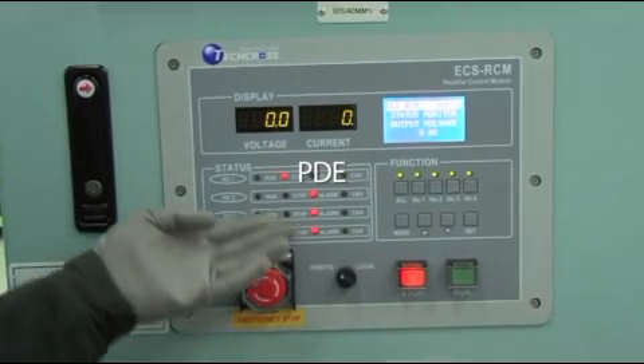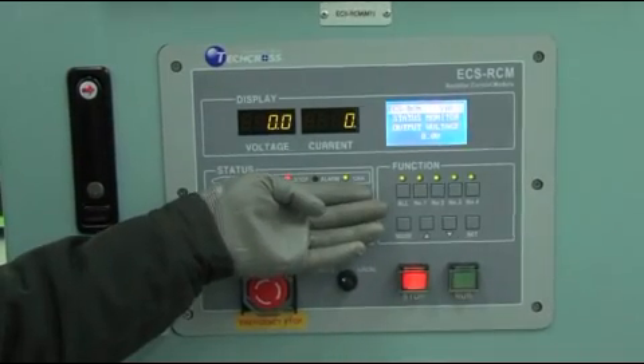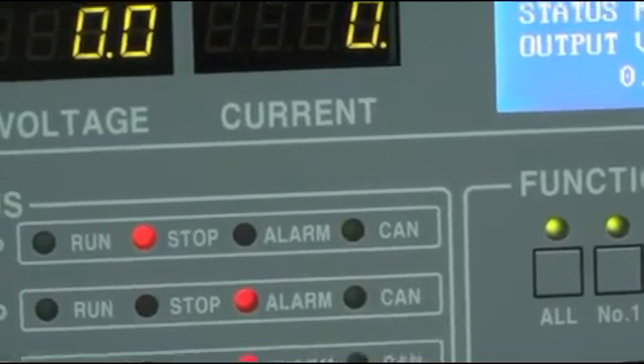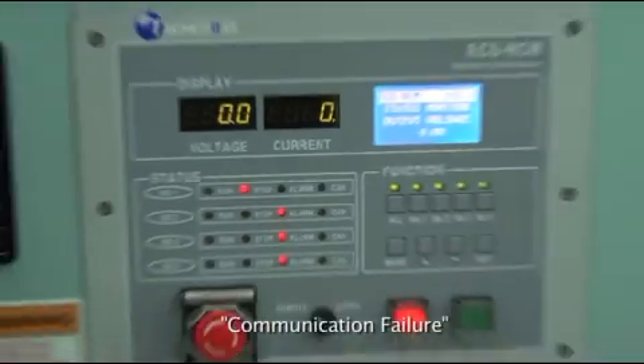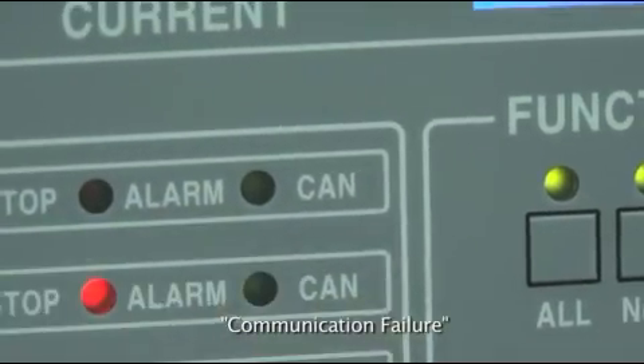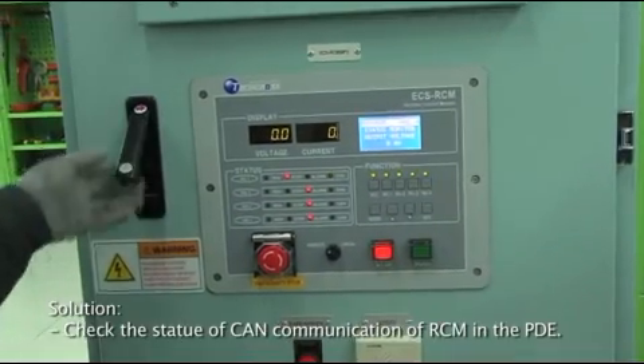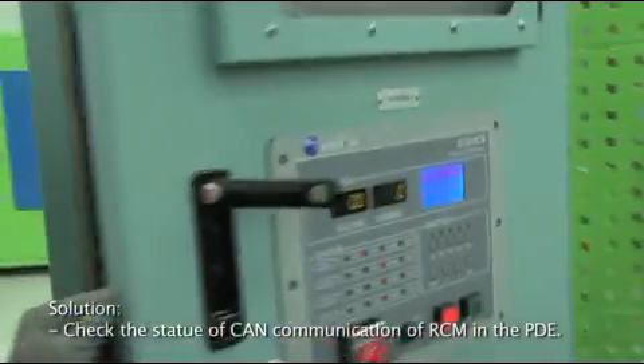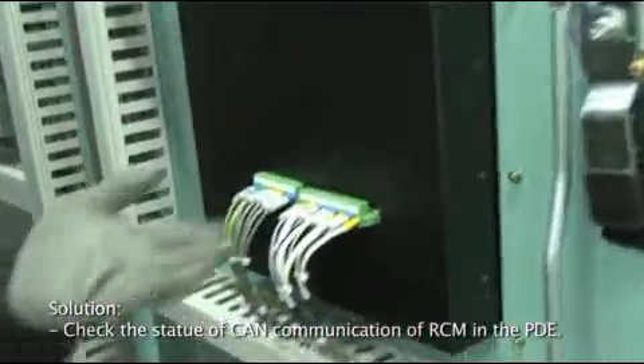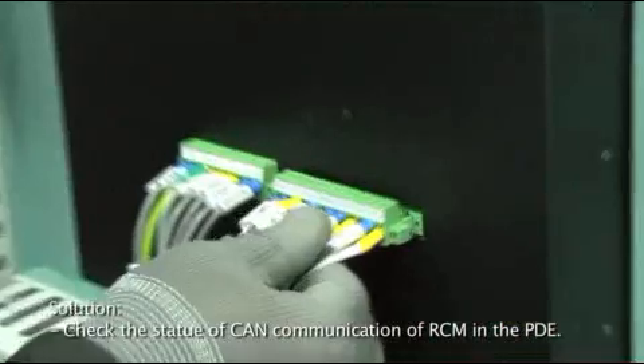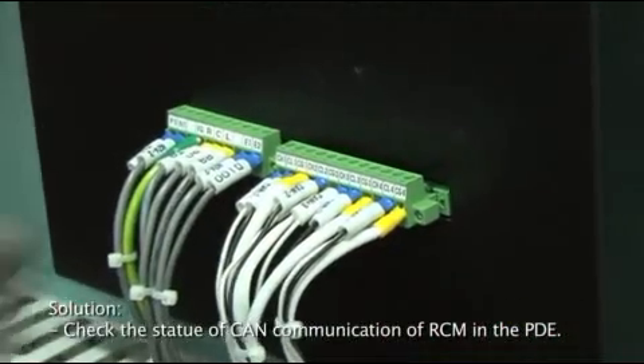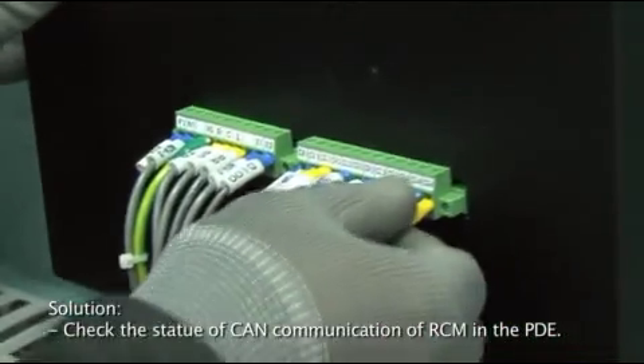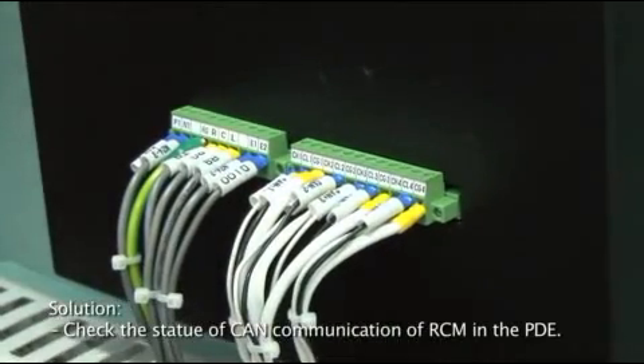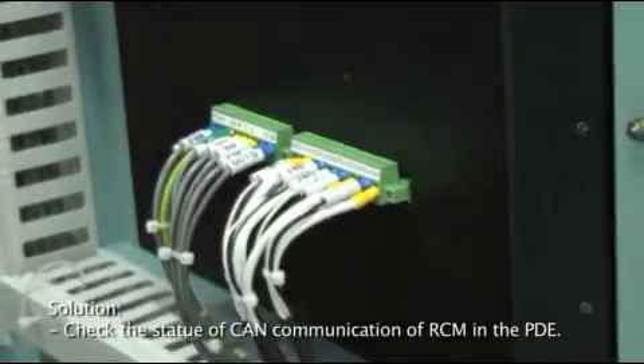2. Troubleshooting for each equipment. 1. PDE. Problem. ECS shuts down 1 minute after alarm message, communication failure, appears. Solution. Check the state of CAN communication of RCM in the PDE. Normal communication mode. CAN LED lamp, green light blinks every 1 or 2 seconds. Abnormal communication mode. CAN LED lamp, light stays either on or off.